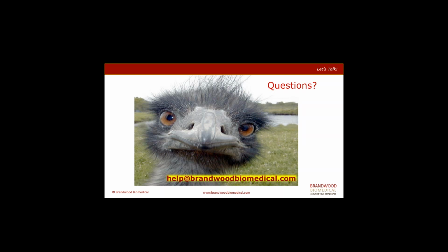Further down, for Romit Singh: is clinical evidence part of design and development, in brackets product realisation clause 7.1, please advise how? Clinical evidence is really the validation aspect of design and development.